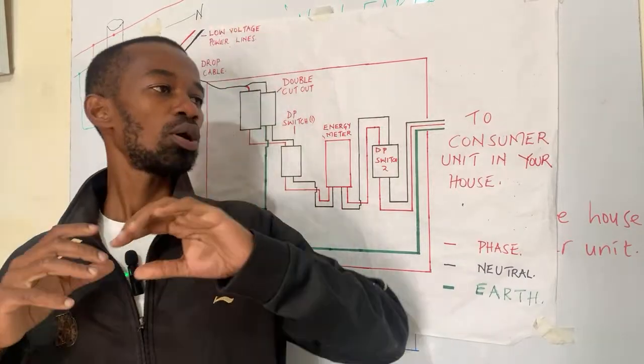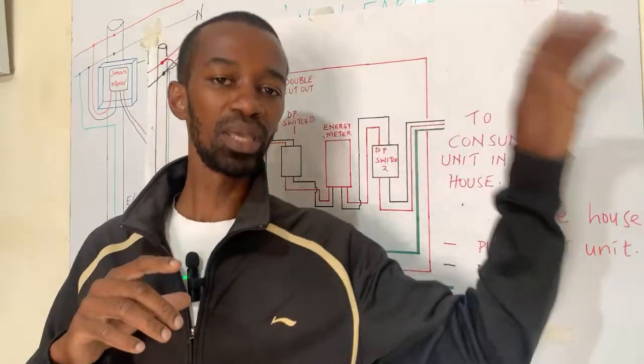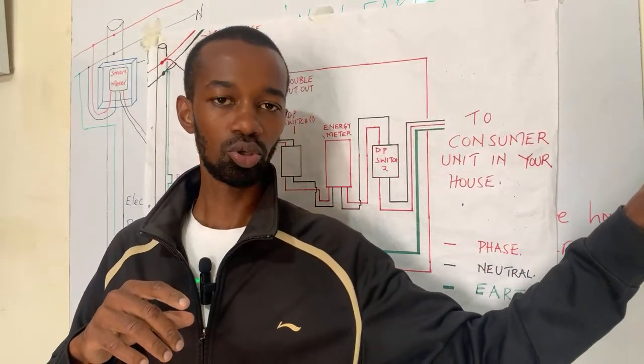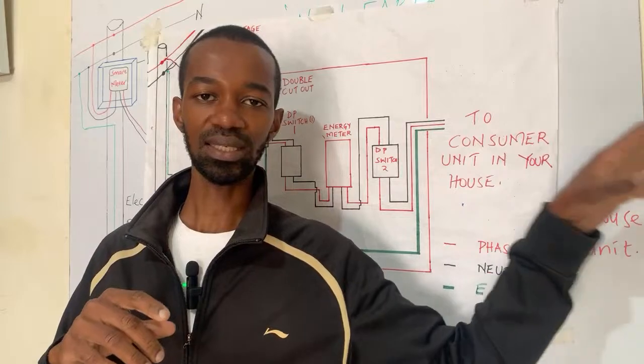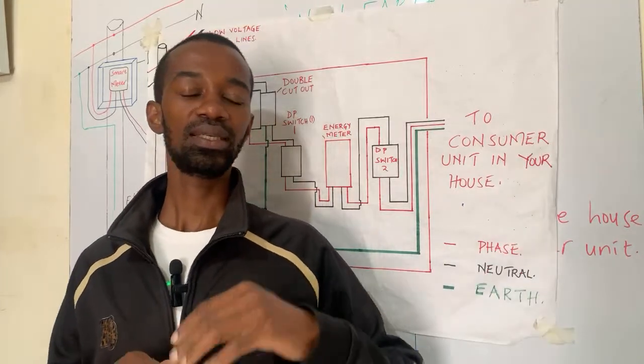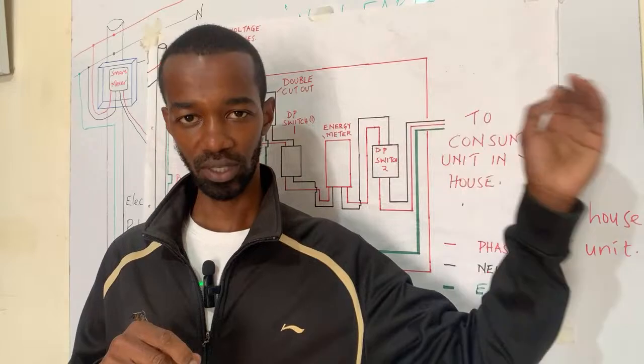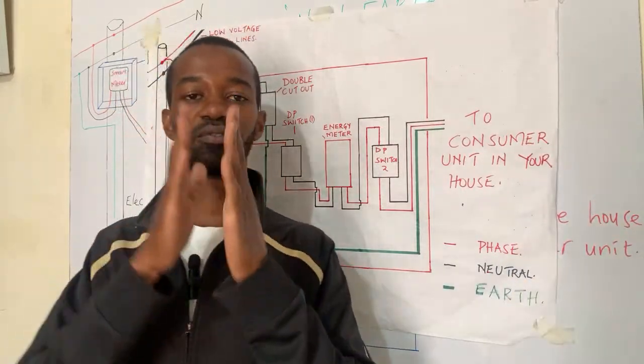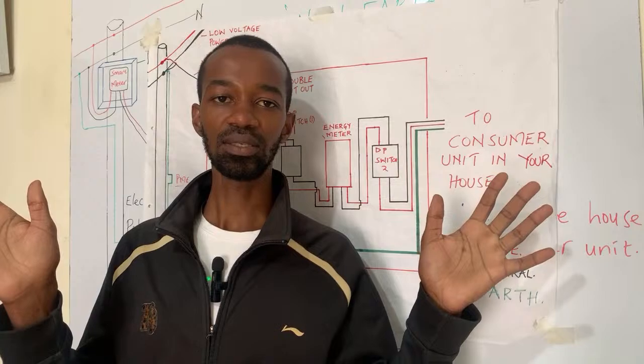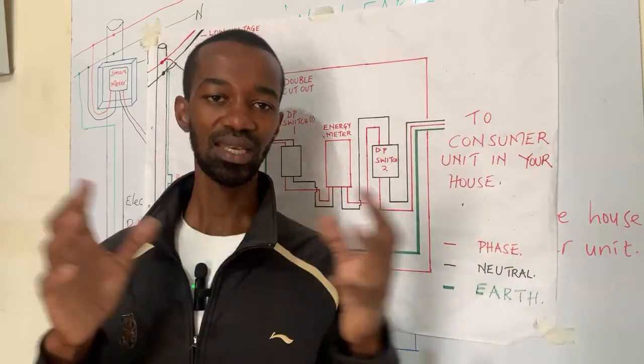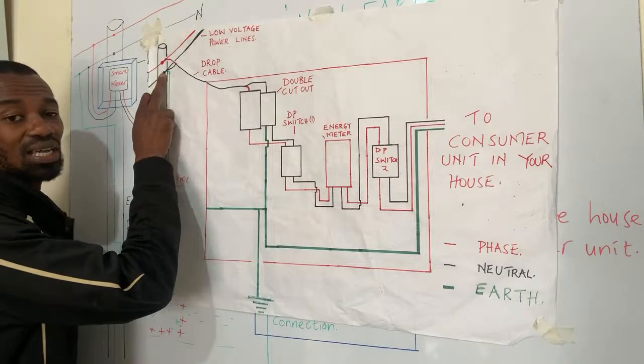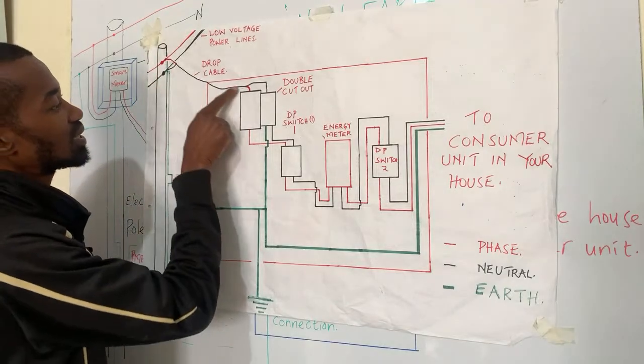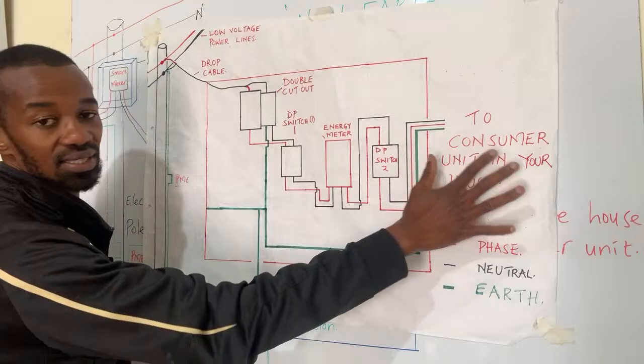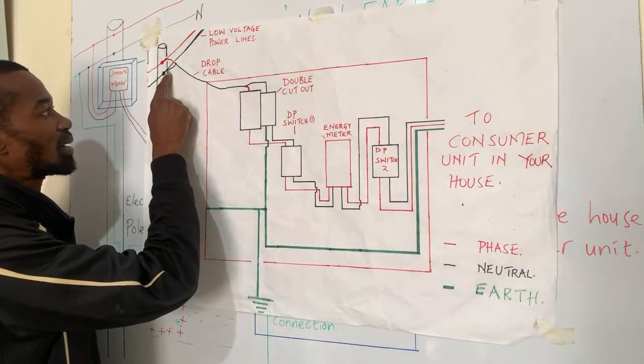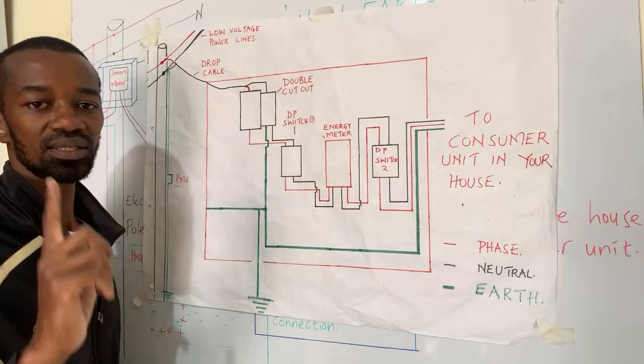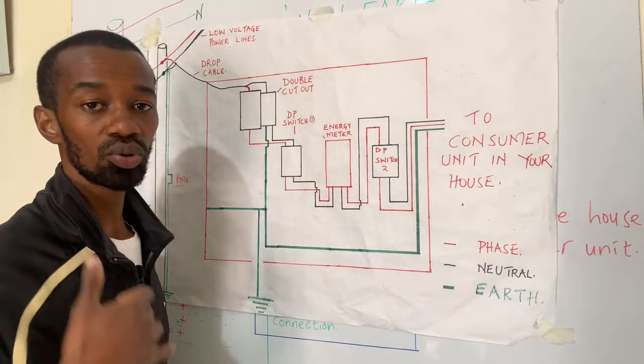For electricity to serve a certain appliance or device at a certain place, it has to go through the phase for it to be returned. If the phase is interrupted, there's no electricity, no shock, nothing. So if the return path is compromised, it means the phase is already present in the system, and the return path has been compromised. That is when someone will receive an electric shock through the neutral.